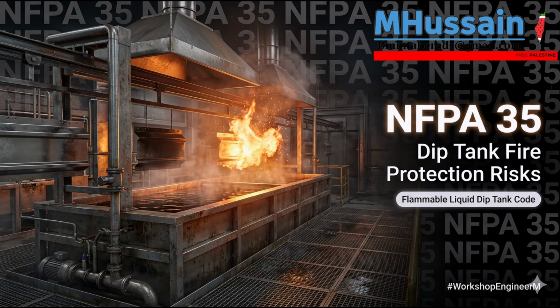If there is a tiny physical gap between the charged pipe and the ground, the electricity will arc across that gap in the form of a spark. And if that microscopic spark occurs in a Division 1 area filled with explosive vapors, you have an instantaneous detonation. The entire engineering goal of Chapter 9 is to build a safe, invisible, highly conductive highway into the earth so that the static electricity never has a reason to jump across a gap and create a spark. Bonding and grounding. This is the science of bonding and grounding.